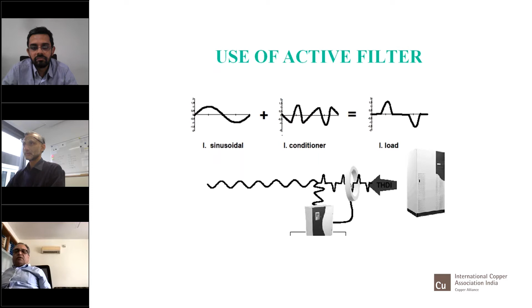So you select a harmonic filter, put it on the upstream side of the UPS. It will filter out all the harmonics and it will draw a perfect sinusoidal wave from the grid or from the input side. And this is how these kinds of problems can be solved.